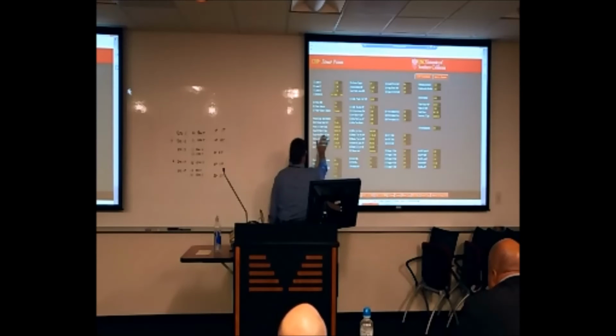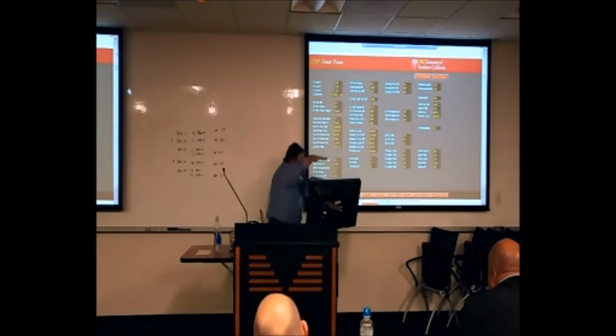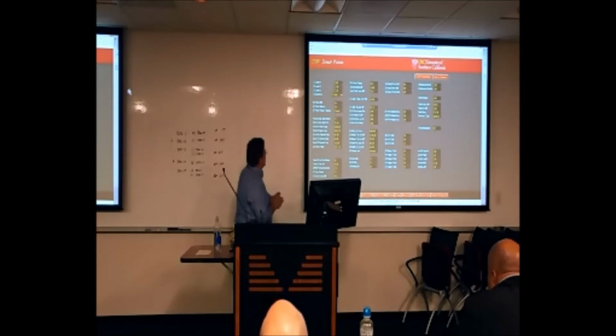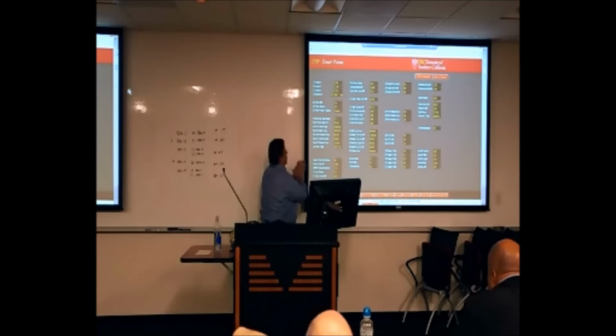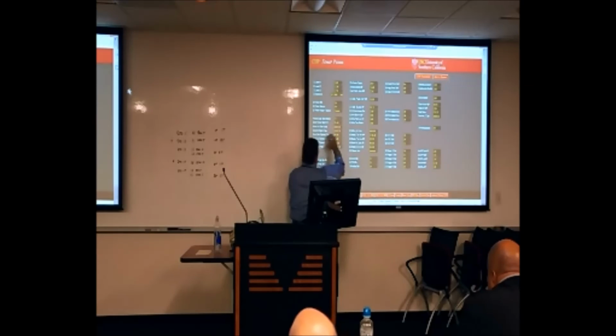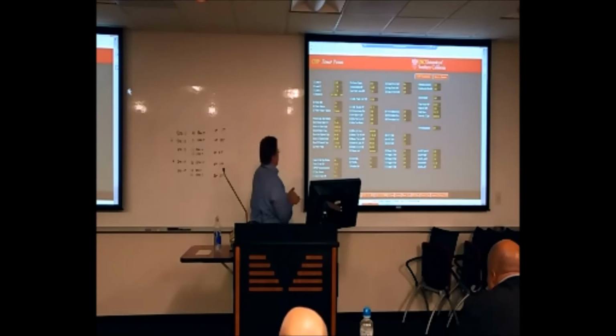So that's why there's a min speed cap and a low speed cap and a high speed cap associated with each pump. And then there are the high GPM caps and the low GPM caps that come into play, but the speed caps are sort of meant to be outside limits to make sure we don't ever lose control of that pump and trip a chiller off. So that would be the variable speed control of the pump. And again, right now it's in the fixed speed control. We're asking for 75%, so we just jump to 75% as we bring on each pump, and that was a safe speed to keep everything safe and stable until there was a good time to throw the switch and make sure it was running okay.